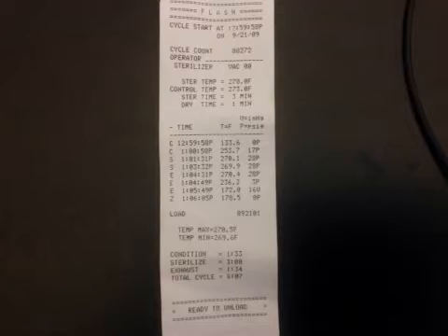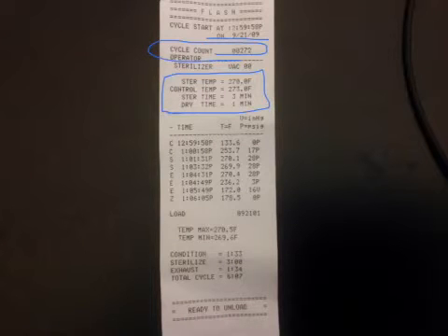You can see on this at the top, it gives an overview of the cycle that is run. So we know this is going to be a 3-minute cycle. Also, it gives you the date and time of the cycle start. It gives you a cycle count number. When you're documenting, you'll need to be able to document the date and time of the cycle initiated. You also need to place on your documentation the cycle count number so it can be connected up with the readout or the record at some later time. And these are typically pulled from the sterilizer on a daily basis and then filed for evidence that the cycle did meet parameters if there was one in which there was a question.